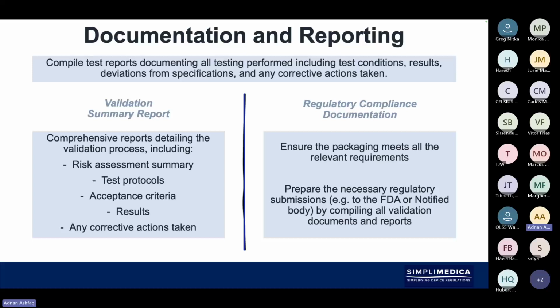So when you've done all of that, of course, you've got to document everything, have a validation summary report, which looks at risk assessment. You've documented test protocols, you've met the acceptance criteria, you have the results, and then you've also looked at corrective actions where required, and then making sure that the documents meet regulatory compliance. So somebody who's in your QARA department would be ensuring that the correct standards have been followed.